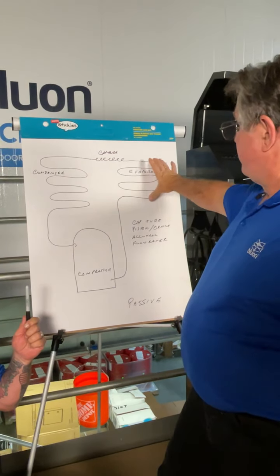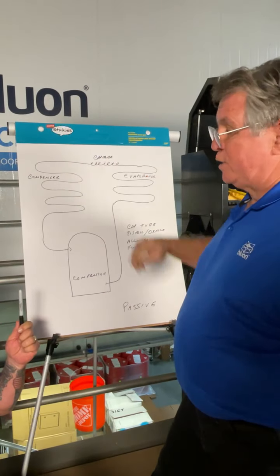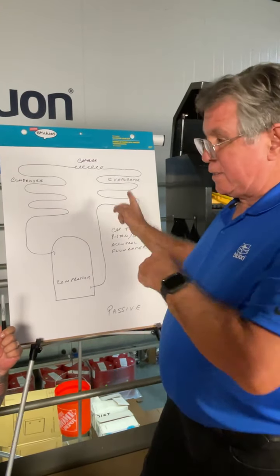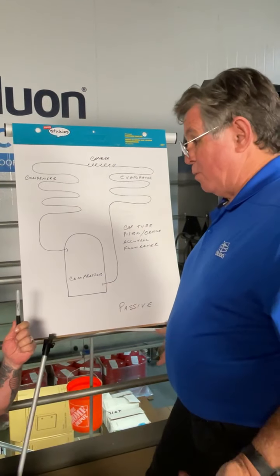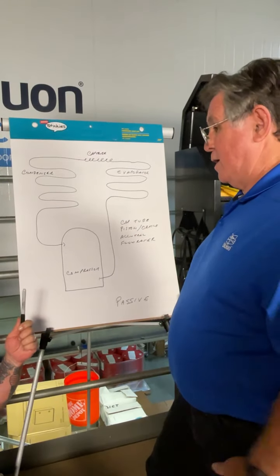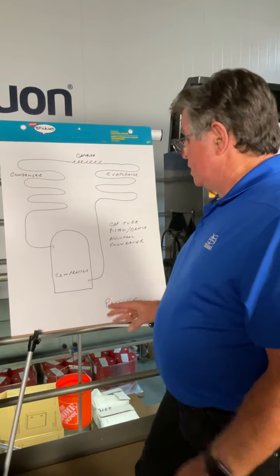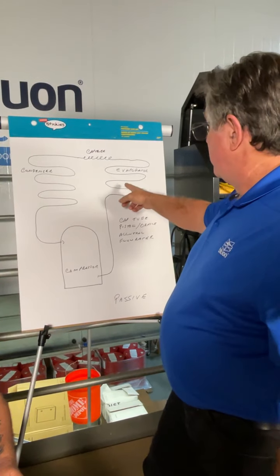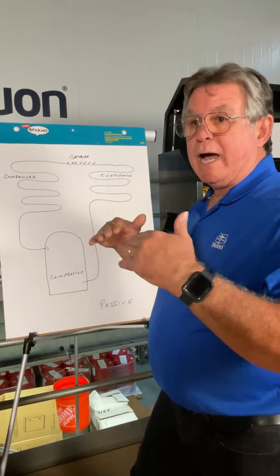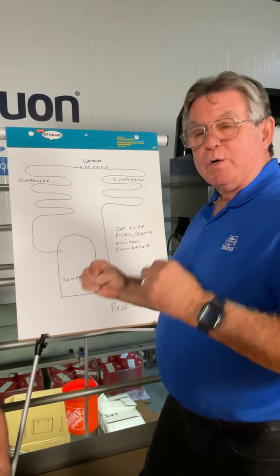What changes the flow through a cap tube: if it gets really cold the pressure drops; if it gets really hot outside the pressure goes up, giving you a higher differential pressure and more flow. Cap tube systems are critically charged - there's only so much refrigerant and when it's maxed out that's all the system can do. Cap tubes, pistons, orifices, AccuRaters, flow raters, and theoretically a manual expansion valve are all your passive devices. Under the right conditions you can end up with a coil starving for refrigerant or a system over-feeding, so you're not consistent on energy usage.